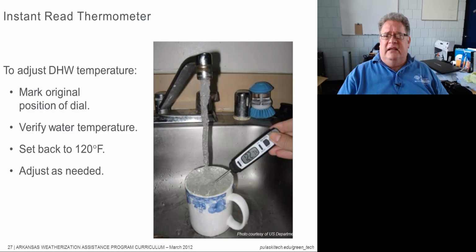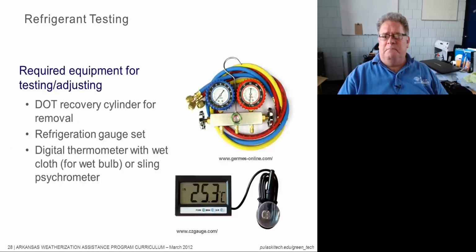All right, refrigerant testing. If you are allowed to do refrigerant testing, then you should probably have a DOT recovery cylinder for removal. You should probably have a good set of gauges, refrigeration gauges, and you should also have a good digital thermometer with a wet cloth for wet bulb or sling psychrometer for testing to be sure. And this is all at a very, very minimum, okay? And those of you that do HVAC all the time, you're going to go, yeah, add a whole bunch more, like a micron gauge, a vacuum gauge, right, okay?